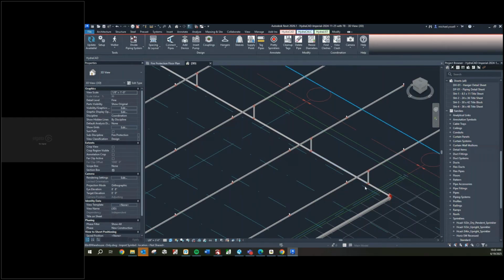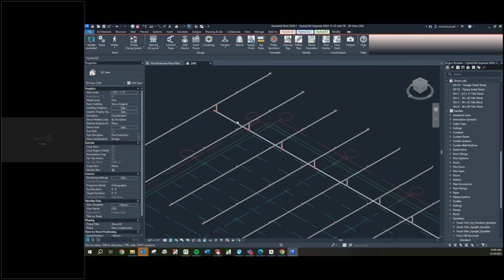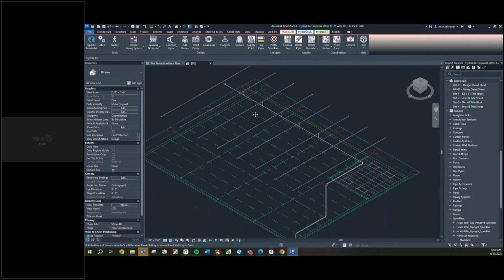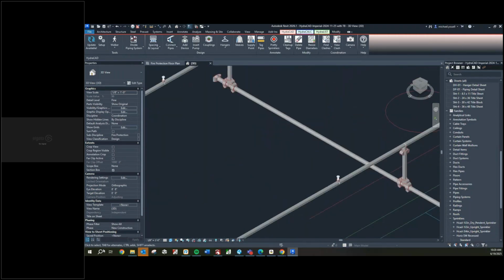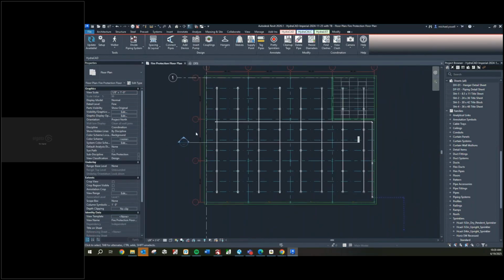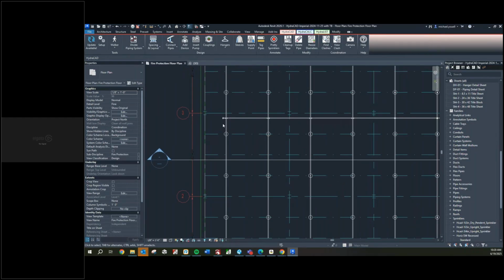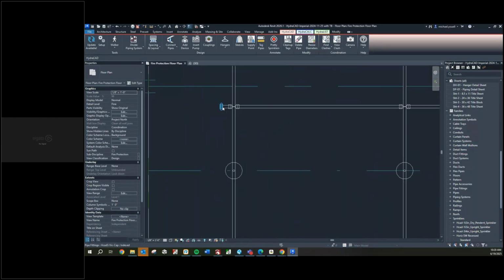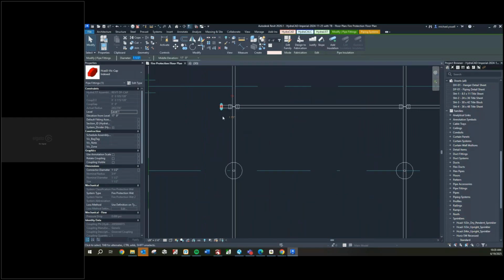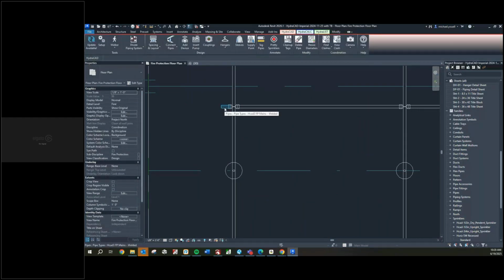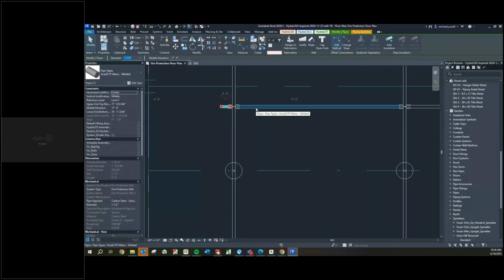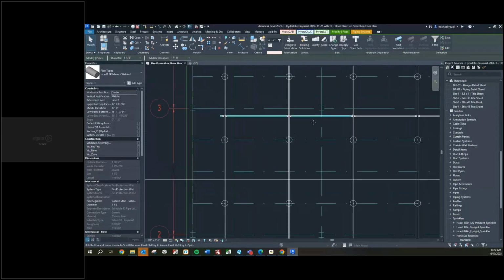And it went back to all 1.5 inch stuff. Maybe there wasn't enough room on the other end. Is that what that picture was? It was complaining at that far end. Yeah. Maybe there wasn't enough room for a fitting. Yeah, I doubt it, but that's the kind of thing that we get yelled at. Erase that cap. Oh, like room here. Gotcha. But if you erase the cap, you could try making those 4-inch. Go select the pipes again and make them 4-inch.